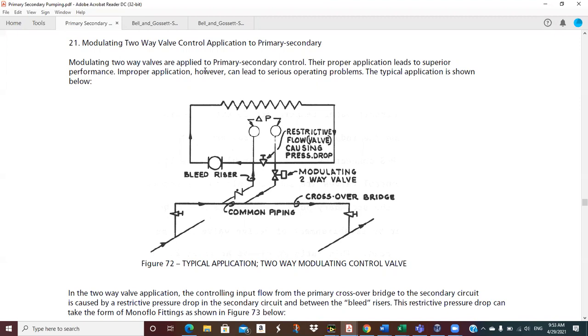So modulating two-way valves are applied to primary, secondary control. Their proper application leads to superior performance, not just good performance, but superior performance. Improper application, however, will land you in court in a lawsuit, which you don't want. I've been there. It's not fun. You don't want to go. However, it can lead to serious operating problems. The typical application is shown below.